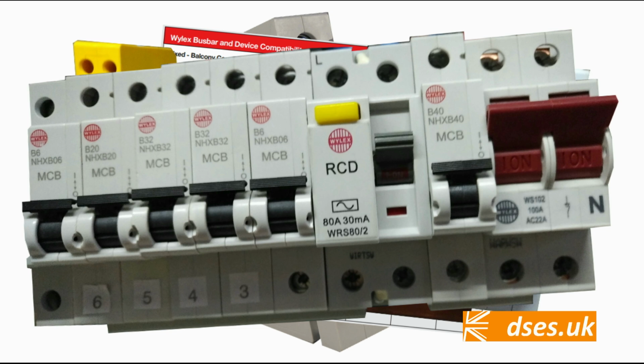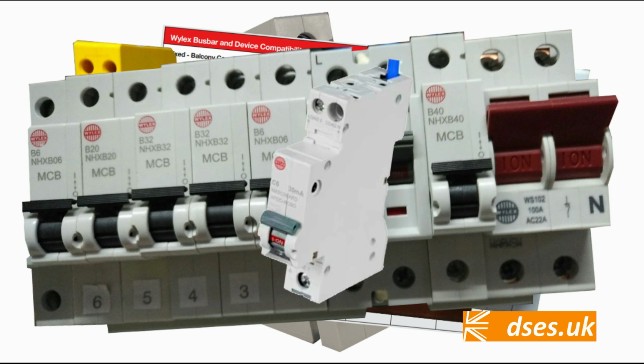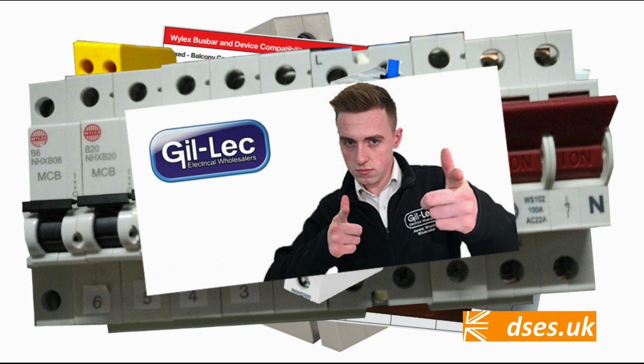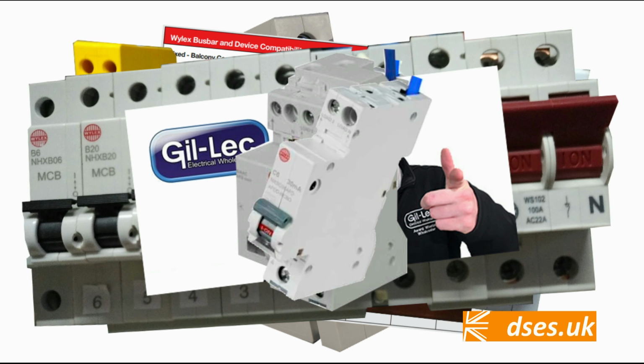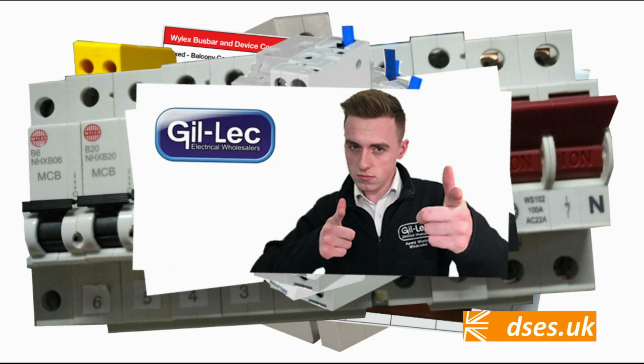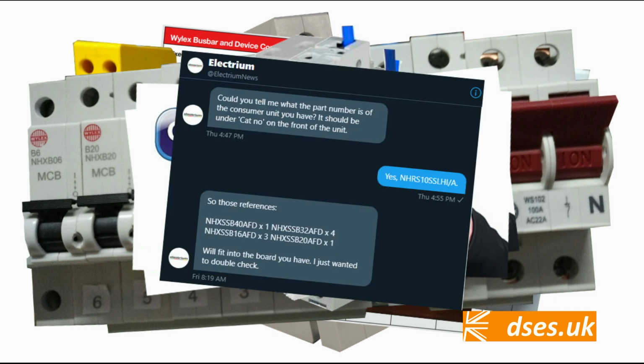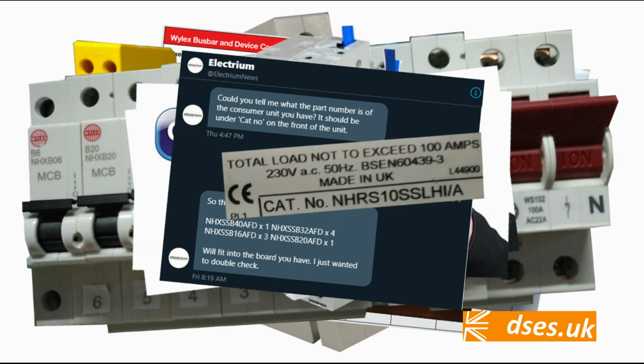However, in trying to find the right AFDDs to retrofit here, I assumed the NHX range of AFDDs would be the ones to go for, yet George at Gil-Lec identified the NHX SS models as being right for the order, but I couldn't find any data on NHX SS, only NHX SC, which is the combined 2-module unit shown in my previous videos that I didn't want as I was after the single unit. So if the C in NHX-SC means it's this combined unit, it stands that the S in NHX-SS is probably the single unit. Therefore George seems to have identified the correct product, and although I couldn't find any data on it, Electrium confirmed to me that NHX-SS was compatible with my NHRS model consumer unit.